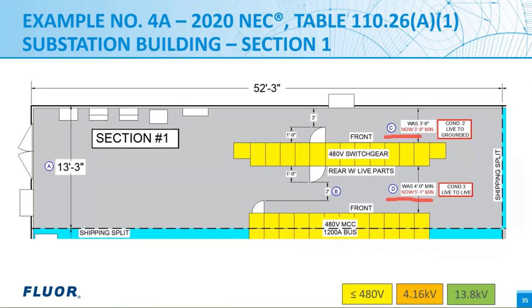motor control centers. We pointed out earlier the parameters for this new rule: it's 1200 amps or more and 1000 volts and less and over 6 feet in length, then it applies. So if this MCC with a 1200 amp rating we see here were to be less than 1200 amps, let's say 800 amps, and the switchgear was less than the large equipment parameters, then this new rule would not apply. You would simply just need to comply with the existing table 110.26(A)(1). And that may be one possible solution in your future designs to save a few inches, especially where space is limited and you can live with a rating of less than 1200 amps in this example.